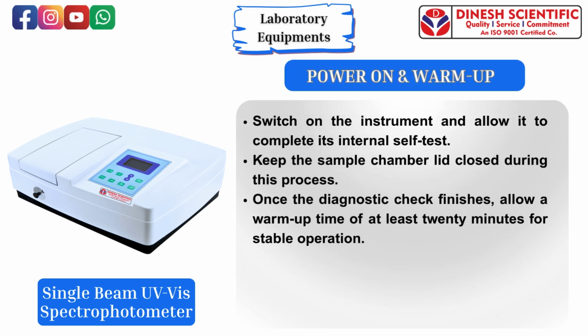Power on or warm up. Switch on the instrument and allow it to complete its internal self-test. Keep the sample chamber lid closed during this process. Once the diagnostic check finishes, allow a warm-up time of at least 20 minutes for stable operation.